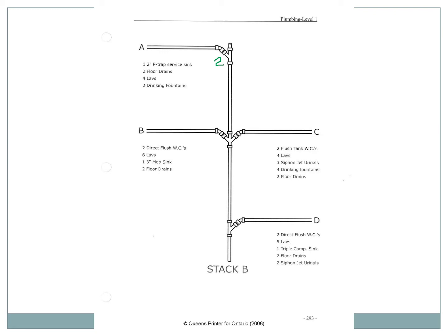That's it. Then next one, you can go to floor drains. That's F, so it's going to be a little bit higher up. Item number 15. Default minimum size is 2-inch. Minimum. I usually use 4-inch, but the code says 2-inch, so we'll go with 2-inch floor drains. There's 2 of them, and they are 2 fixture units each, which gives you a total of 4 fixture units.